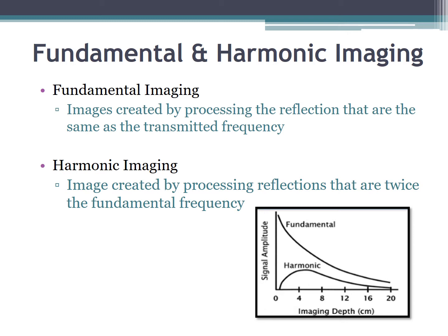So fundamental imaging is created by only listening for fundamental frequency reflections. Fundamental imaging is really good for penetration, not so good for superficial imaging, and it's also at kind of that mid-range depth of imaging. So fundamental sometimes really helps us out with getting that sound beam really far into the body.